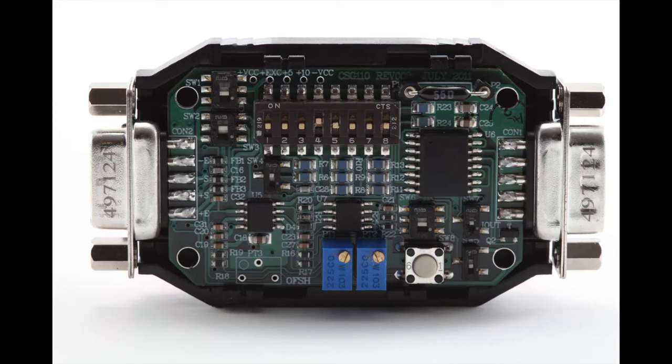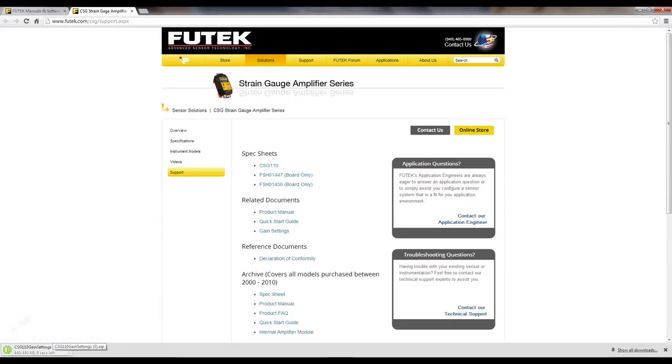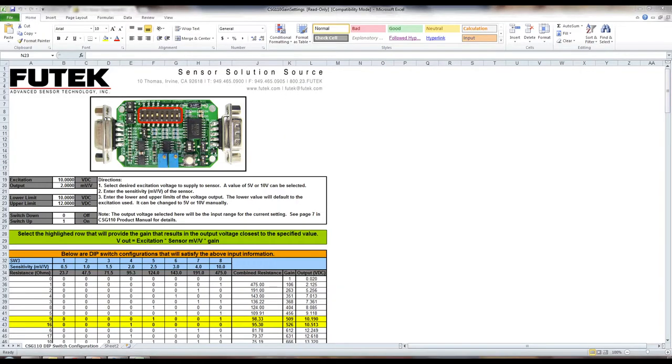So now we will be setting up the gain. In here, you can see under related documents there is a gain settings file. If you click the gain settings, you can download the file and use it. Once you have downloaded the gain settings spreadsheet, you can specify your excitation, your sensor's millivolt per volt output found on your sensor's calibration certificate, and the lower and upper limits. Note that the lower limit will adjust automatically. The upper limit is used because the gain should place the output of your sensor and the CSG110 between the lower and upper limit, allowing you to fine-adjust the output using the span potentiometer on the CSG110.